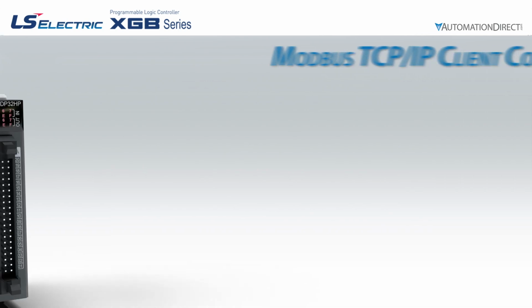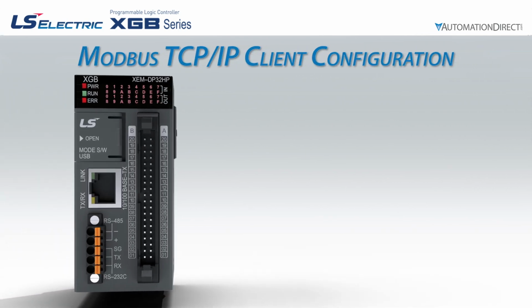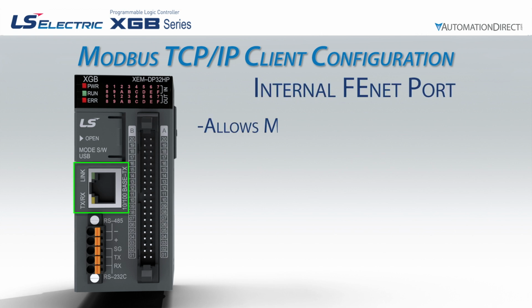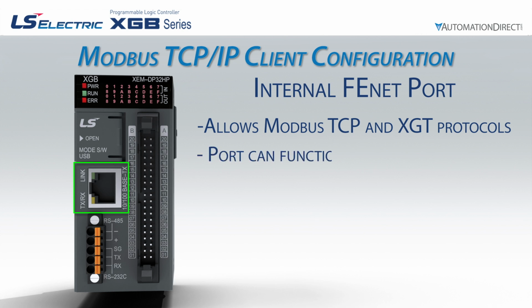The XGB PLC offers many ways to communicate over Ethernet. The onboard Ethernet port is referred to as the internal FENet and allows Modbus TCP and XGT protocols. For Modbus TCP, the PLC allows configuration as both a Modbus slave and master.